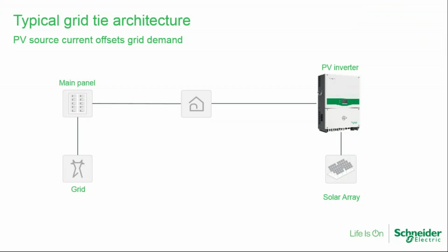So most of you guys, I'm probably covering territory that you already know, but in the latter part of 2010 and earlier, we did a tremendous number of string inverter, PV inverter installations that powered the loads, and then any surplus power was sold back to the grid. And they gave us pretty good programs to sell power back. In some cases, they were too good and were dropped as soon as they expired. Ontario rings a bell. So this is basically how the PV inverter was connected up to the main panel.